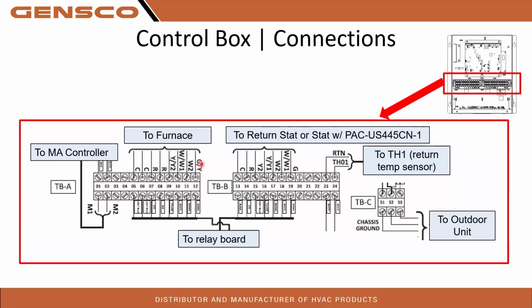You'll notice on here, and we'll get into this a little bit later on, you have a G/Y. Depending on whether you're using single stage or 2-stage: for single stage, you're going to hook G and Y on your wiring. If you're going to do 2-stage, you need to do G and first stage together, so G and Y1 together, and then Y2 over here. Most 24-volt furnaces require the G to be energized in order for Y to work. So that's why we have that down there.